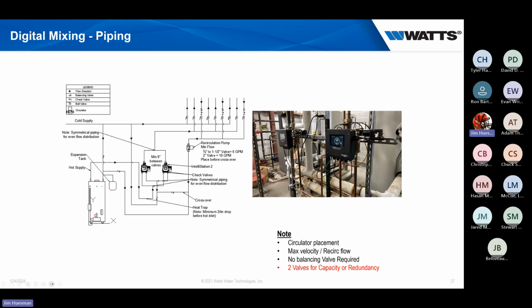We're also able to add jumper cables over, so maybe instead of working off both, we can lead-lag on both systems if we've sized these correctly. Dual valves have really saved us a tremendous amount of time in emergencies - like with an entire university, or working with Cincinnati Public Schools a lot. If it goes down, there's a lot of screaming and yelling when we have extremely hot or extremely cold water. So it gives us the ability to add two different valves that talk to each other, work together, and let us troubleshoot.